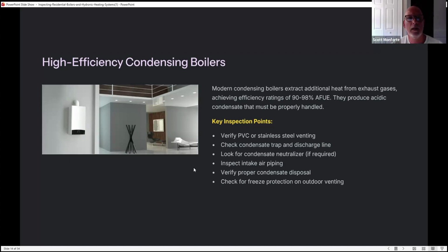I always mention it. And to Jim's point, if it is a septic, you don't want acidic condensate going into that septic. But usually, if it's just air conditioning condensate, you can go outside. But because now all these high efficiency tankless water heaters, combination water and heat, they want that condensate to go into a moisture trap within the house so it doesn't freeze. And every once in a while, I'll see it going outside, and I'll make note of it, or you'll see it if it's real cold, if it's freezing up.